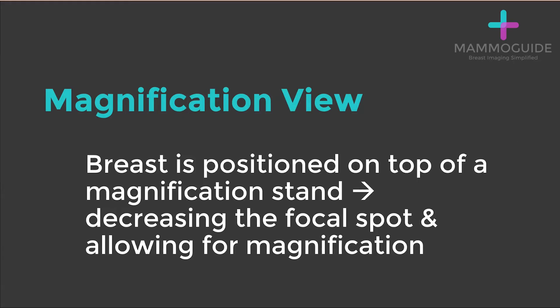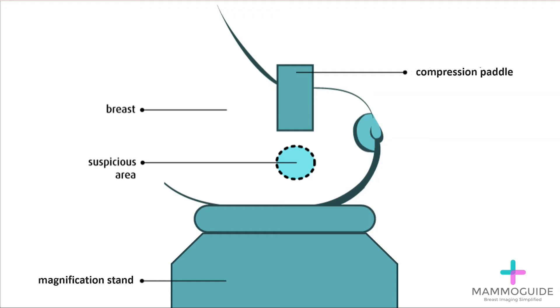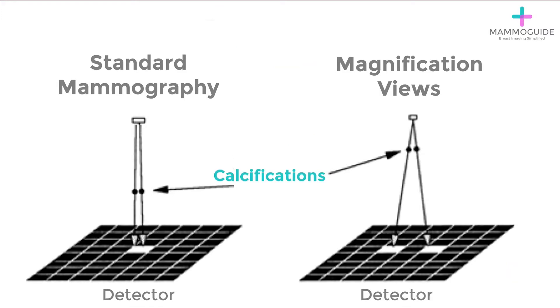In a magnification view, the breast is positioned on top of a magnification stand, not directly on top of the detector plate. This decreases the focal spot and allows for magnification. Here you can see that the breast is elevated and then compression is applied. The abnormality, often calcifications, are positioned closer to the x-ray source and further away from the detector.